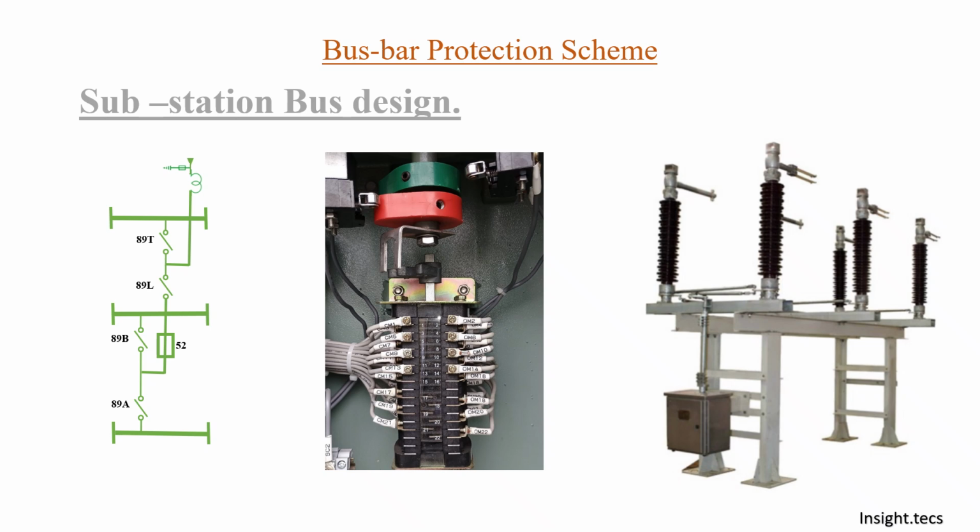On the open operation of the isolator, a few contacts will be open. On the closed operation of this isolator, some number of contacts will be closed. And again, there will be some vice versa contacts also that will operate in the reverse position. Based on that, the decision will be taken whether the isolator is open or closed, and that signal will be used for busbar protection scheme.